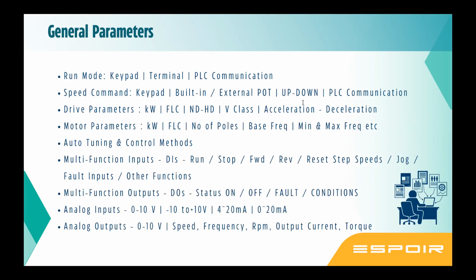Now, these are the general parameter sets you can do. Run mode. Now, how are you going to run the VFD? You connect to the VFD, you connect to the motor, you have selected properly, sizing done, everything is done. Now, there are some features: you can run the motor just from the keypad, on, off, forward, reverse direction, you can select just on the keypad. Now, with the keypad, generally there are issues that the operator can damage it. Continuous usage of a keypad can probably damage the system. So people go for a terminal, means a push button. So you can take out the on-off condition to a terminal. You can also do it through a PLC. So you need to define first how you are going to run the VFD.